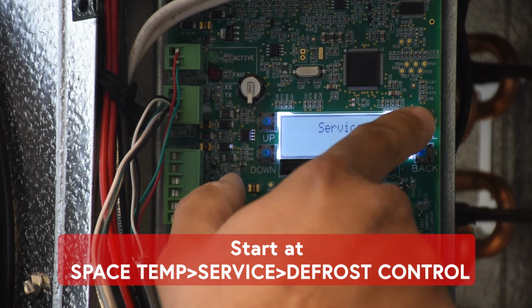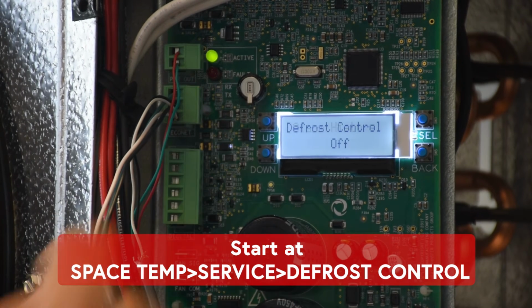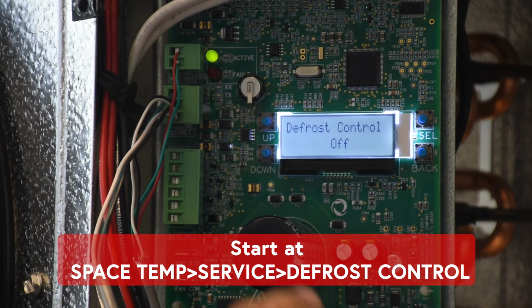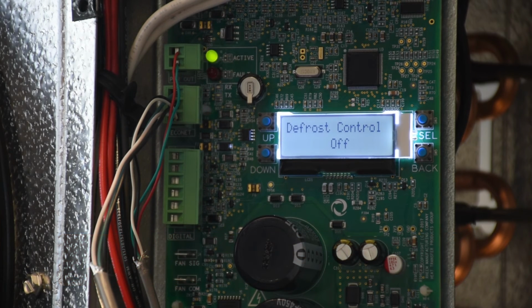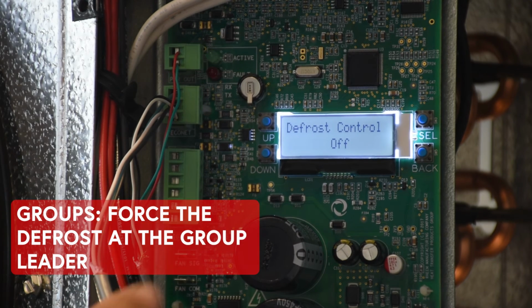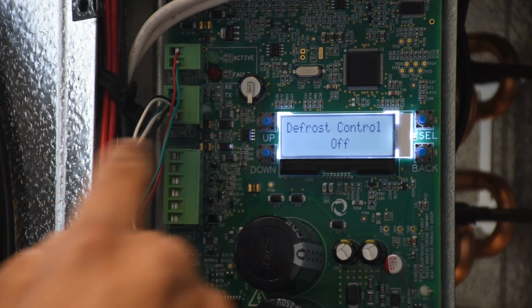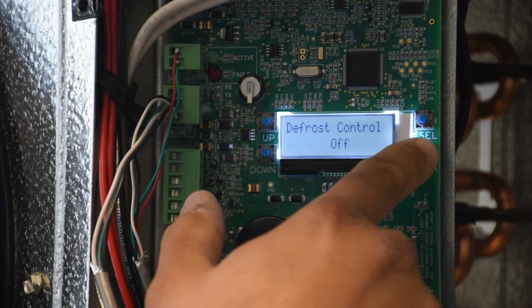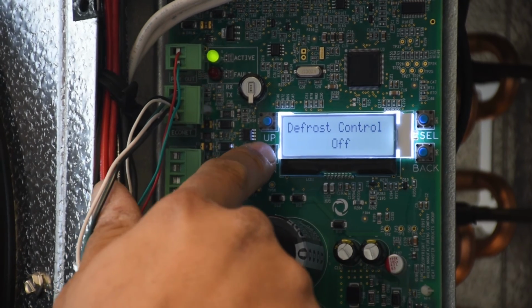So you basically go to service and then scroll down to defrost control, and in here one thing to keep in mind is if it's a standalone unit, you can just go ahead and force a defrost right then and there. If you're working with a group, you need to force a defrost at the group leader in order to get the entire group to defrost simultaneously. So in our example here, we have a leader. So we just go here, go to start defrost, and hit select.